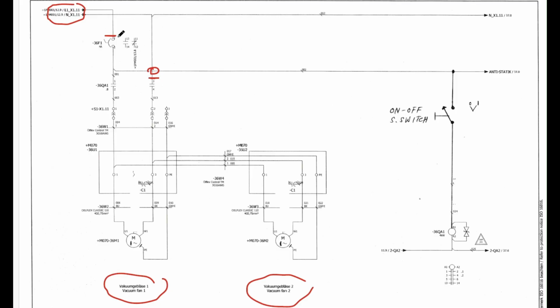If we get supply voltage here, let's suppose 120 volt, then the next step is this: what is this? This is the single pole circuit breaker of 4 ampere, 36F1 single pole circuit breaker. Then we will check voltage here. Remember, the black probe is permanent here. The red probe here gets the voltage, and here also we get the voltage. Then we connect the probe here. What is this? This is the auxiliary contact of 36QA1. What is 36QA1? That is this one, the magnetic contactor.